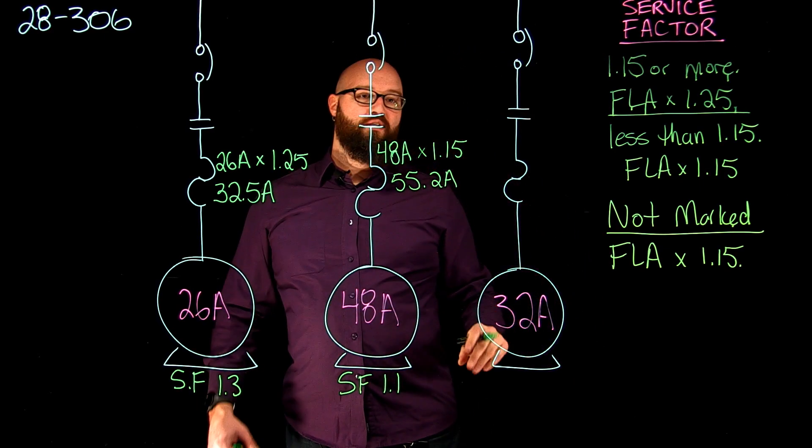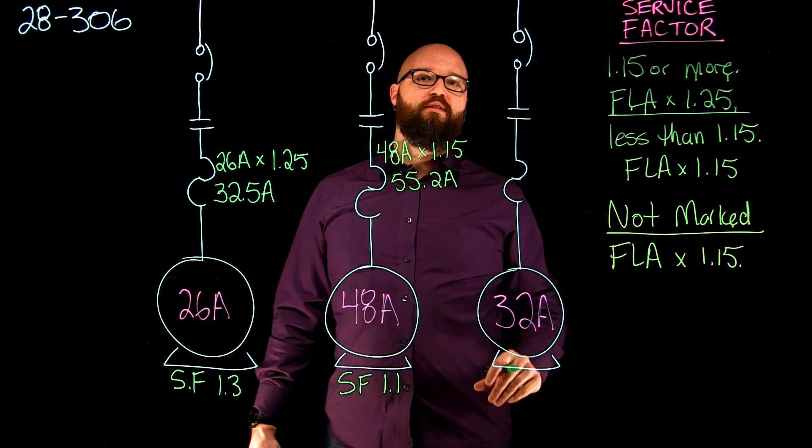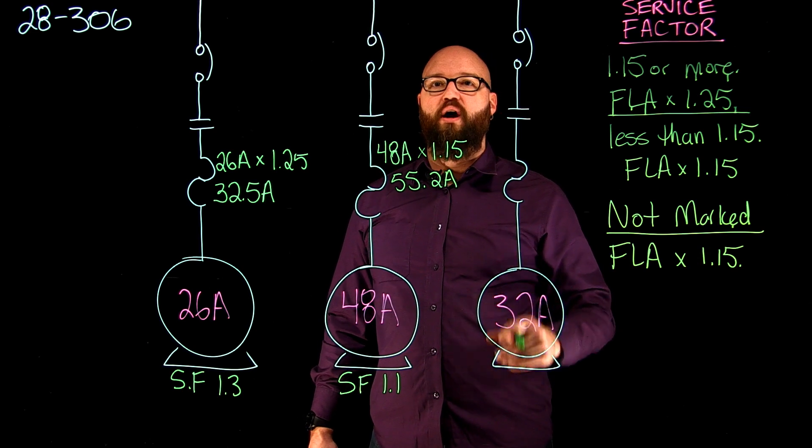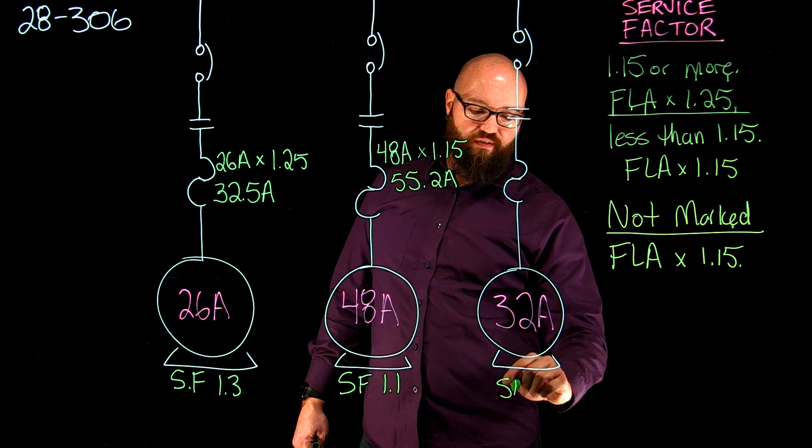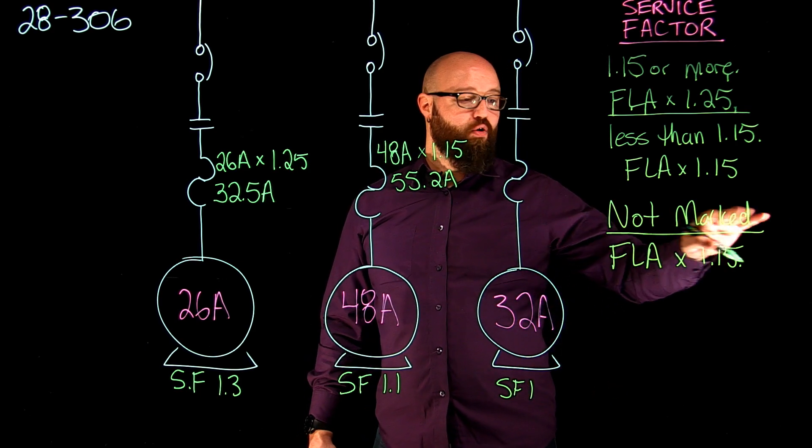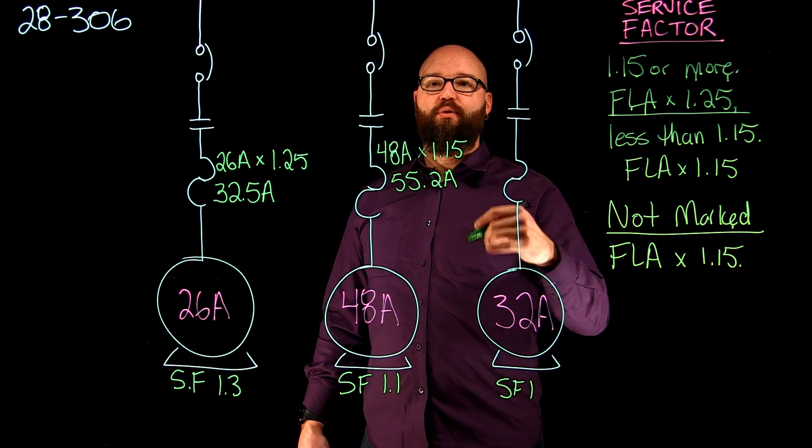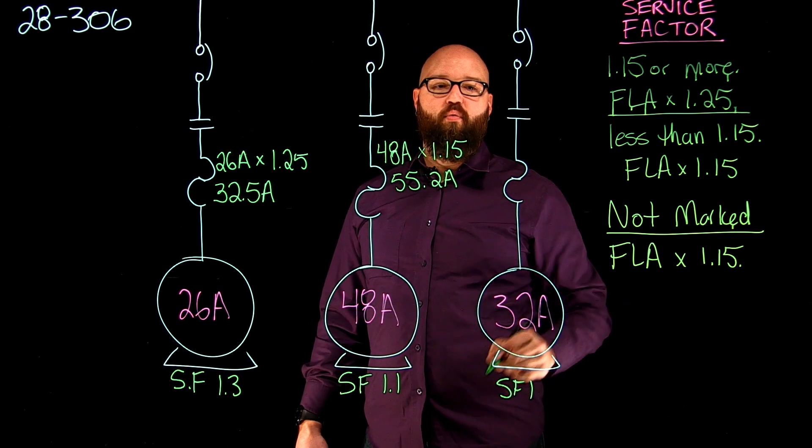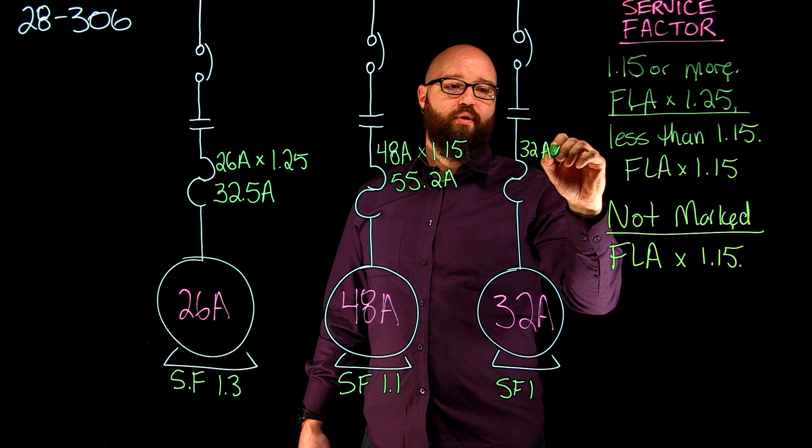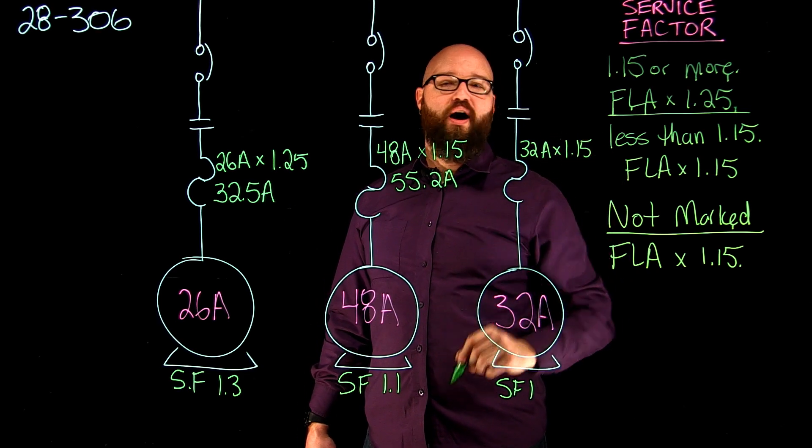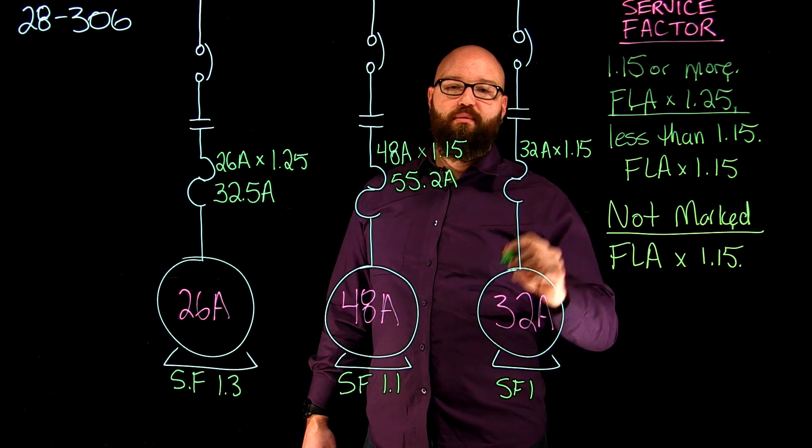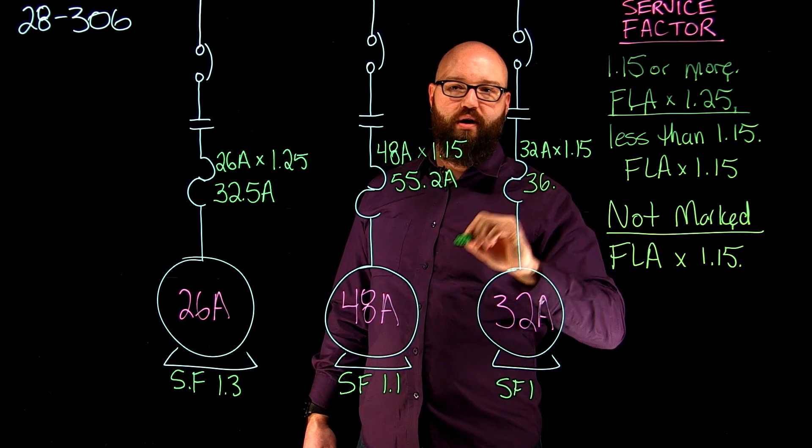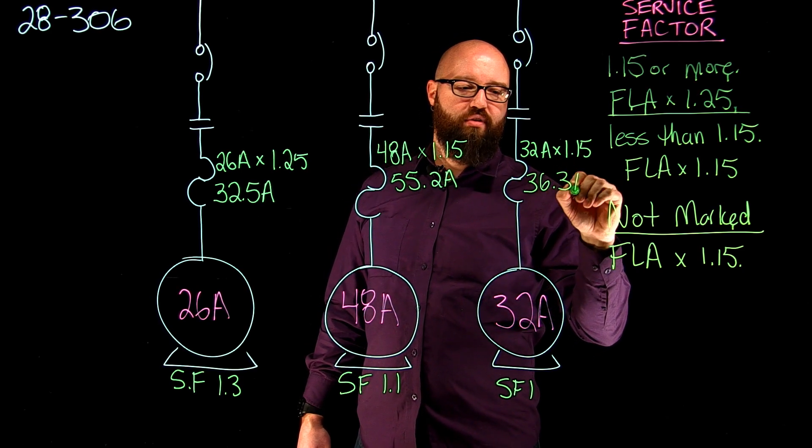Our third motor does not have a service factor marked. So again, as mentioned here, if it's not marked we're going to assume a service factor of 1. If I have a service factor of 1, it falls into the category of under 1.15, so we would apply the same percentage multiplier that we did for our service factor of 1.1. So we're going to take our 32 amps and multiply it by 1.15, which gives us our maximum overload setting of about 36.3 amps.